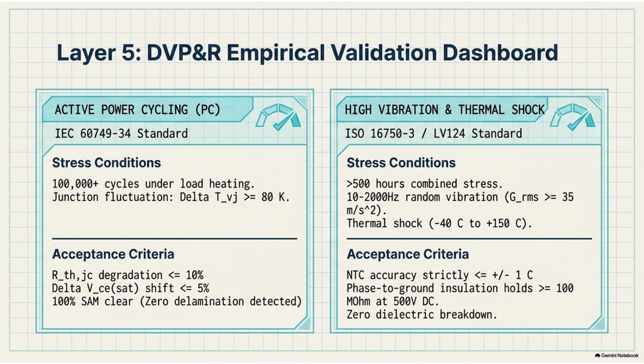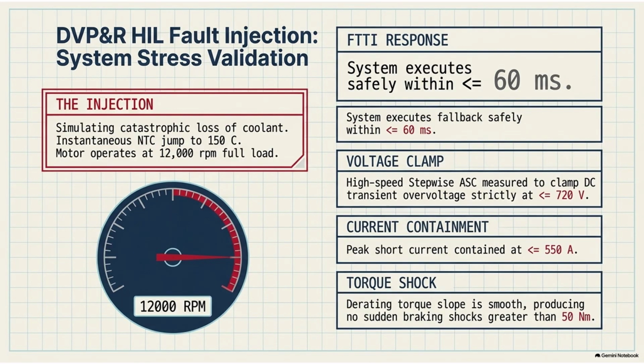It tests the absolute thermal mechanical limits of the nano-silver sintering and those ultrasonic wire bonds we talked about. They are trying to force the metals to shear and fatigue. And the acceptance criteria at the end of the test are incredibly strict. After surviving 200,000 extreme thermal shocks, the engineers measure the thermal resistance of the module. It is not allowed to have degraded by more than 10% from its brand new baseline. The electrical voltage drift across the power chips must be less than or equal to 5%.